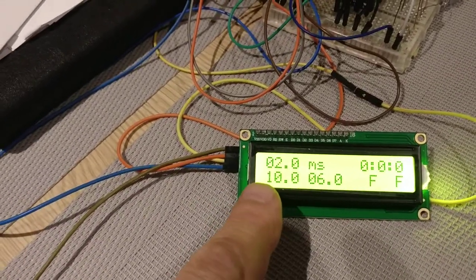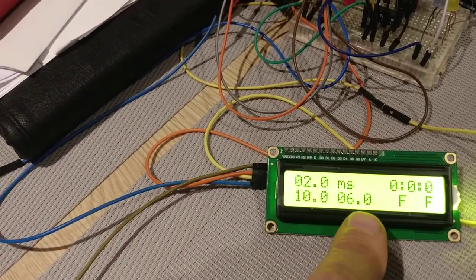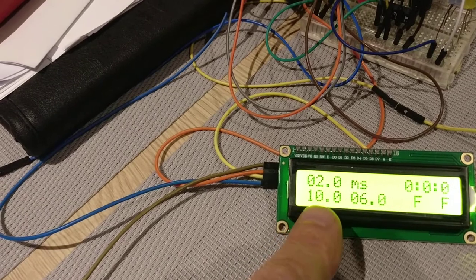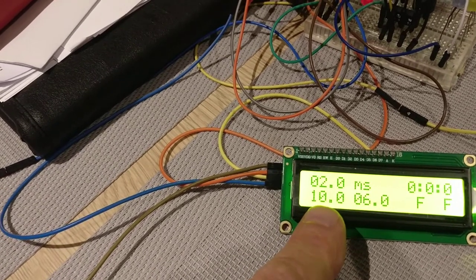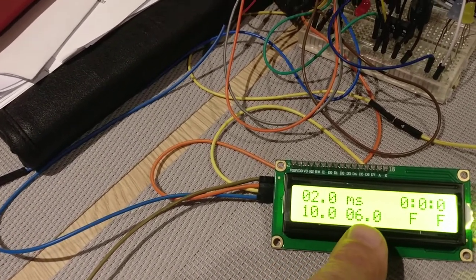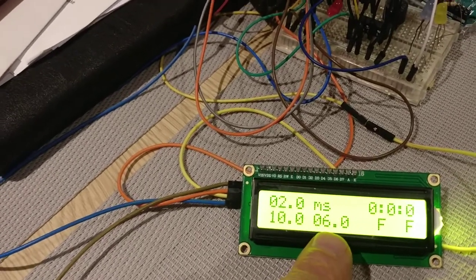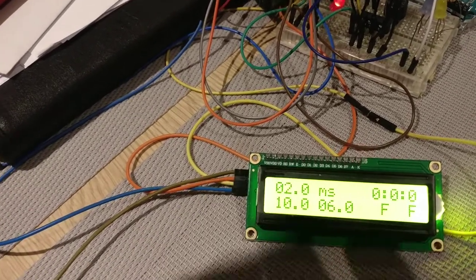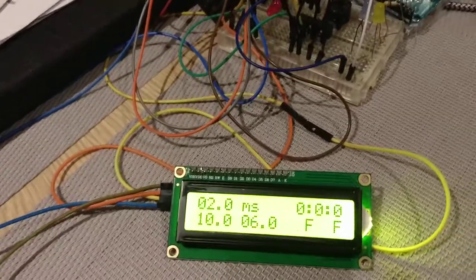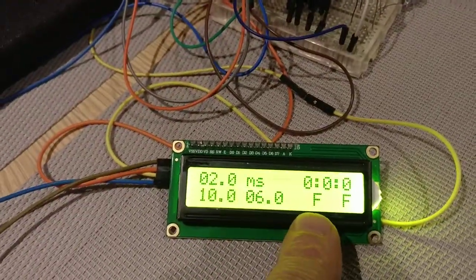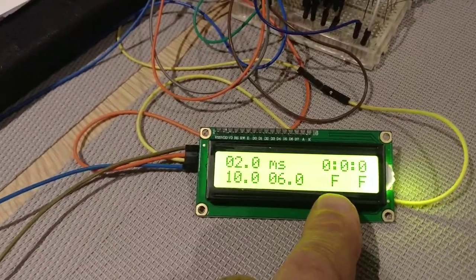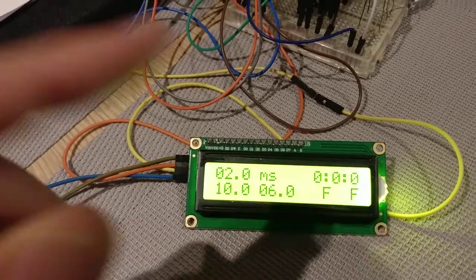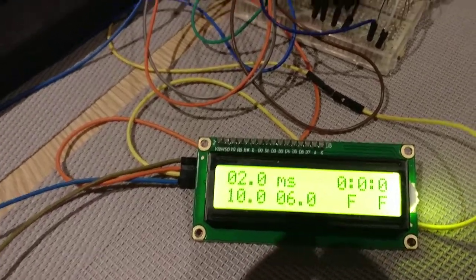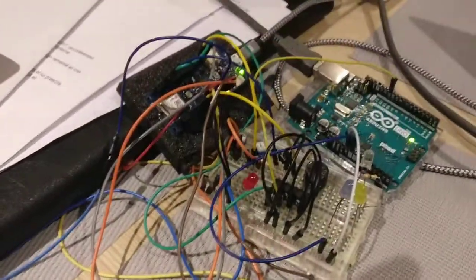These here are the limits for wind speed. So when the wind reaches 10 meters per second, the shutters will automatically open. And if the wind gets down again to 6 meters per second or lower for a certain amount of time, the shutters will then close again. This is the false. False means we have not opened the shutters, and false, we have not closed the shutters. So the shutters are in basically any old state, the state they were in when they started. As you can see, the limit is 10.